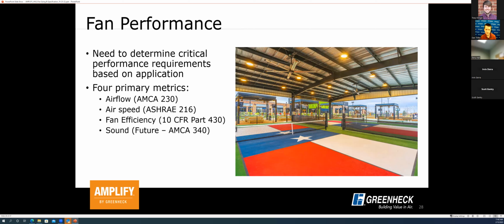For fan efficiency, the standard is actually a federal regulation. So it's in the Code of Federal Regulations, Part 430. This is an efficiency metric and an efficiency test procedure that was defined by the Department of Energy and is a minimum requirement in order to be able to sell HVLS fans in the United States. So the metric that's used there is called CFEI, the Ceiling Fan Energy Index. It's very similar to the fan energy index, if you're familiar with that on other types of fan equipment. The only difference is that the requirements for HVLS fans are twofold. You have to have a minimum CFEI value of 1.0 at full speed and a minimum CFEI value of 1.31 at 40% speed.